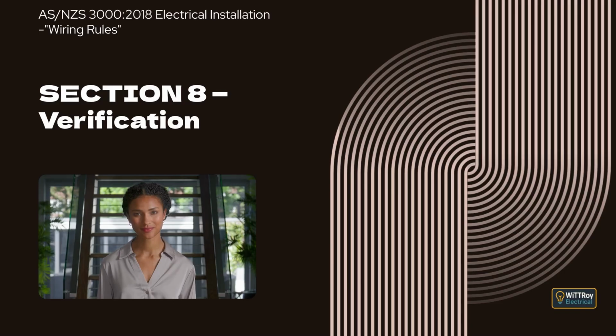Clause 8.3.9.2.2 Supply available. This clause explains that where supply is available, the earth fault loop impedance for each branch of each final subcircuit is measured using an earth fault loop impedance tester. The test is carried out at the socket outlet that is furthest from the supply on each branch of the final subcircuit. The clause also states that the MEN connection must be left intact during this testing.